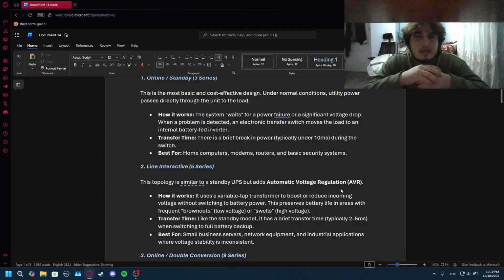It basically means that you can still use the main AC source even if the voltage has harmonics in it, up to a certain point, of course. It regulates low and high voltage. Transfer time: like a standby model, it has a brief transfer time, typically 2 to 5 milliseconds when switching to full battery backup. Best for small business servers, network equipment, and industrial applications where voltage stability is inconsistent.